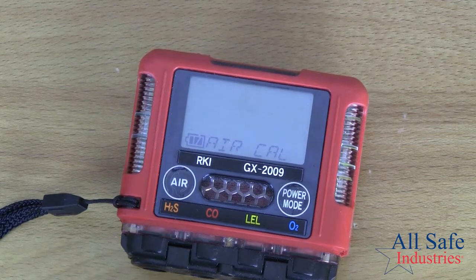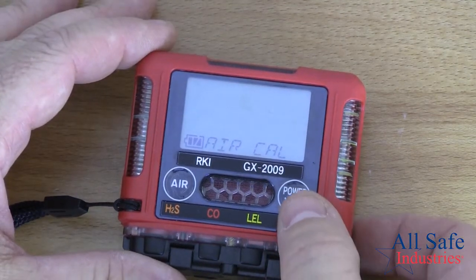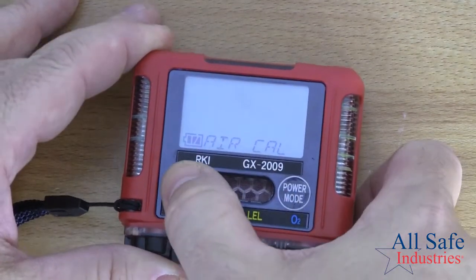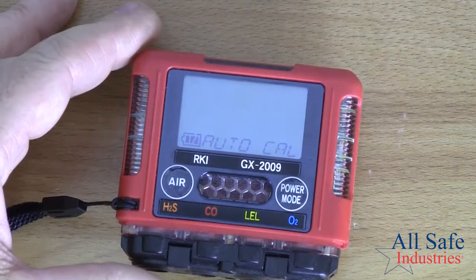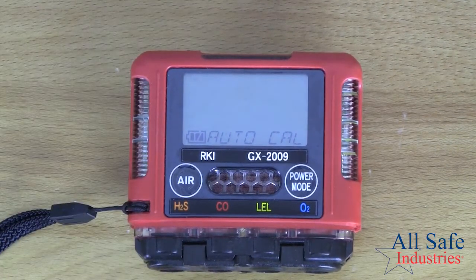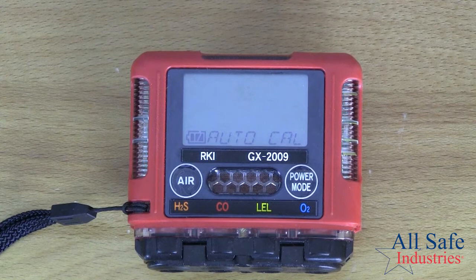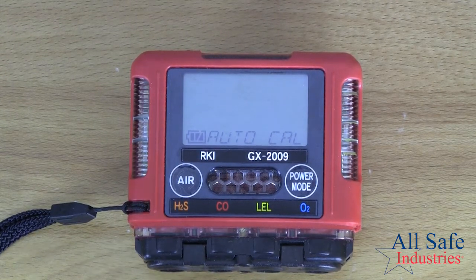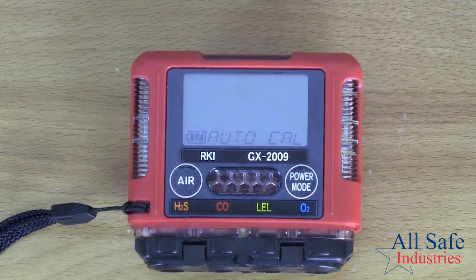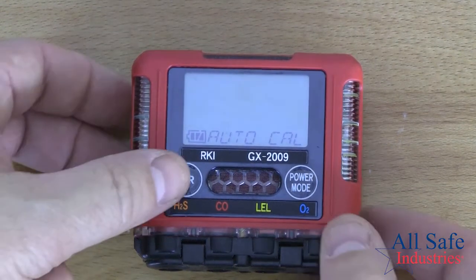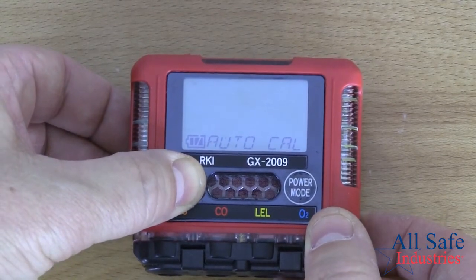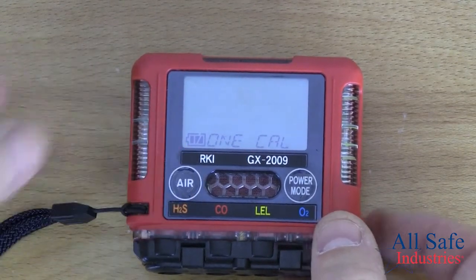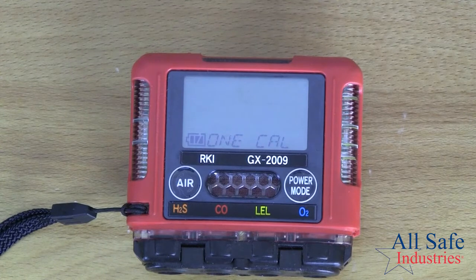Now if I want to calibrate the instrument, that's on the next menu. I press the air button to scroll to the next main menu, which is auto cal. And this is the menu I'll come to if I want to calibrate the instrument. And of course, if I press the power mode, I'll go into the auto cal sequence, and then I'd be able to calibrate, and I'll do that in the next video. If I don't want to do an auto cal, I can press my scroll button to go to the next menu, and the next menu is the one cal.